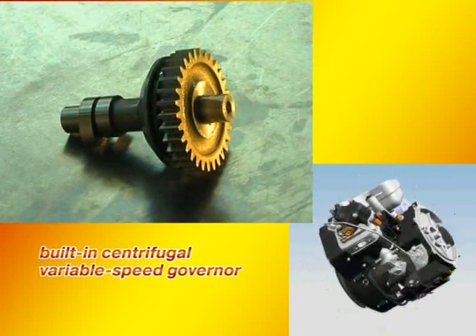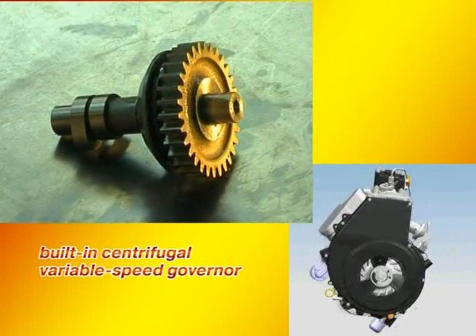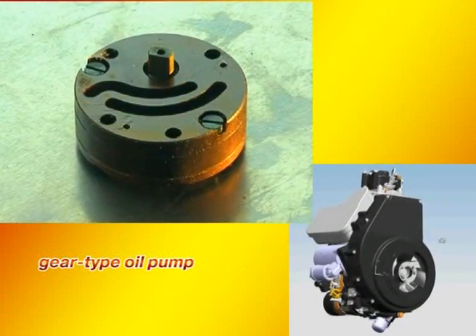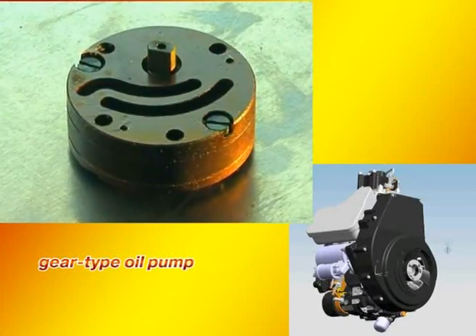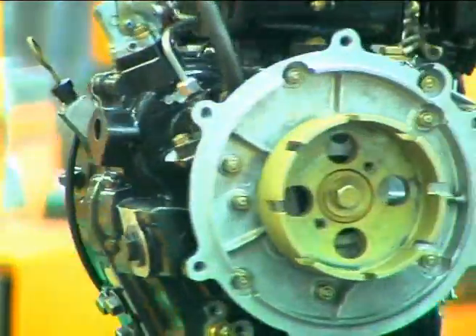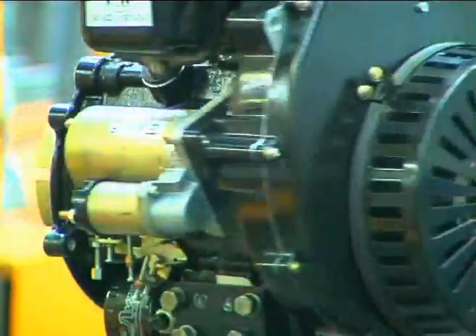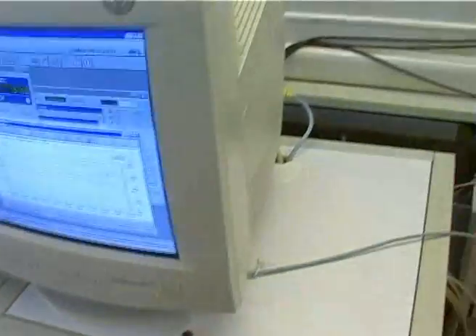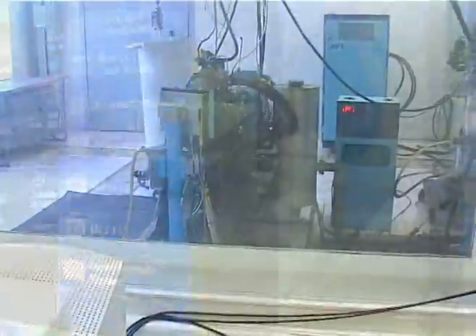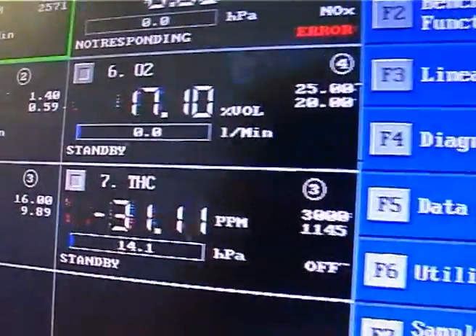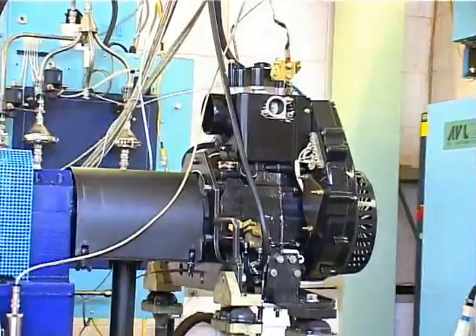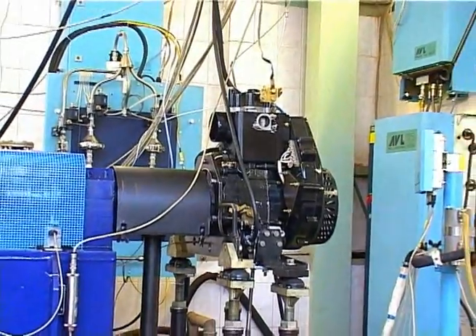A built-in centrifugal variable speed governor keeps the specified speed conditions. A gear-type oil pump ensures lubrication of crankshaft and crankpin sliding bearings. Diesels can be equipped with a built-in crankcase oil heater and a crankcase oil cooling system with distribution unit. This package makes diesels capable of working within ambient temperature ranges from -50 to +50 Celsius degrees. Each of the presented diesel models has a standard row of modifications.